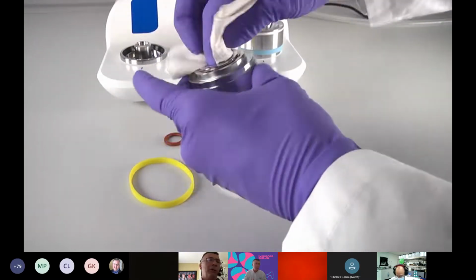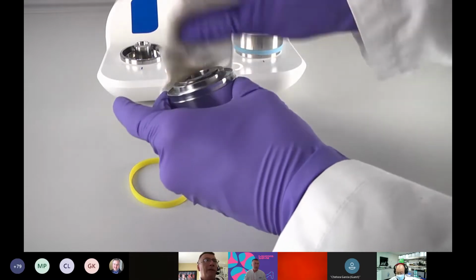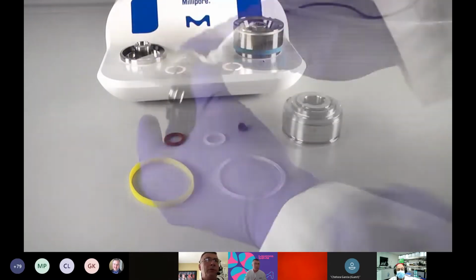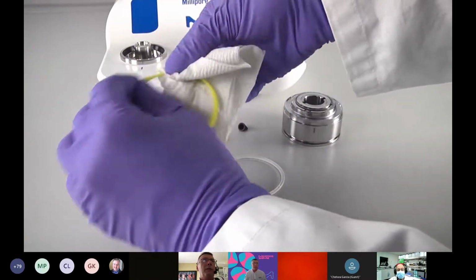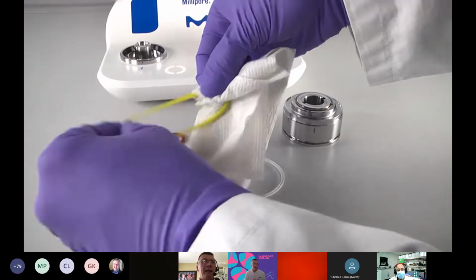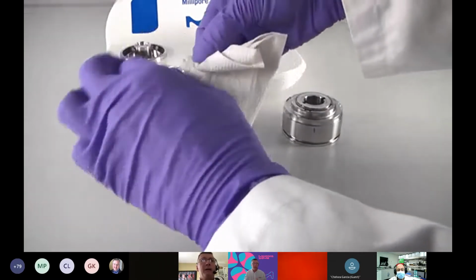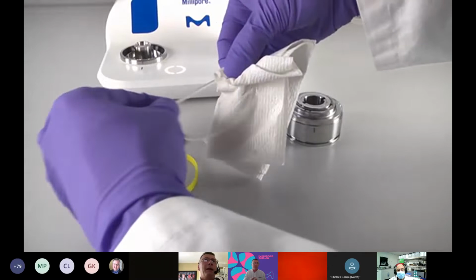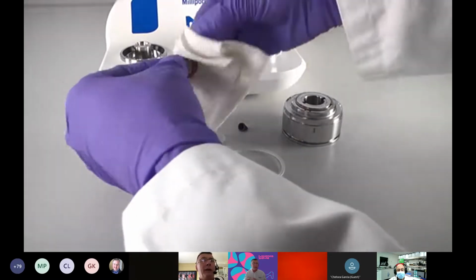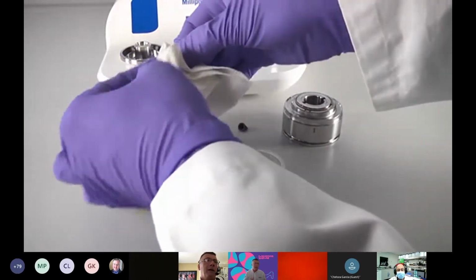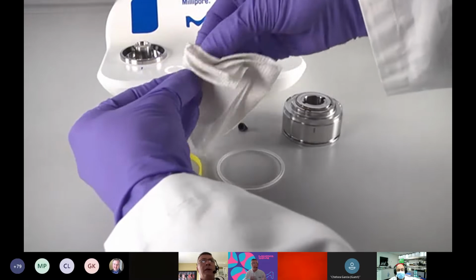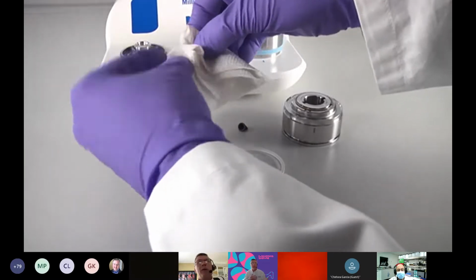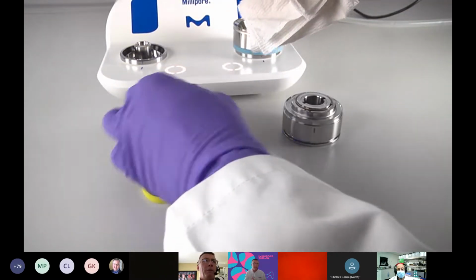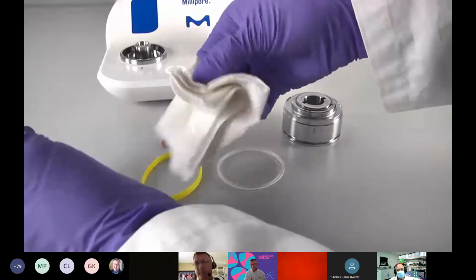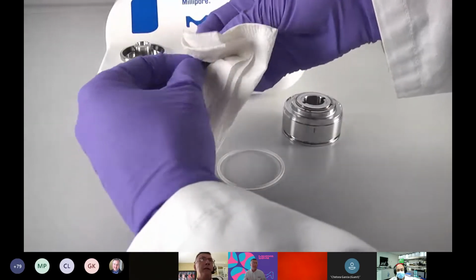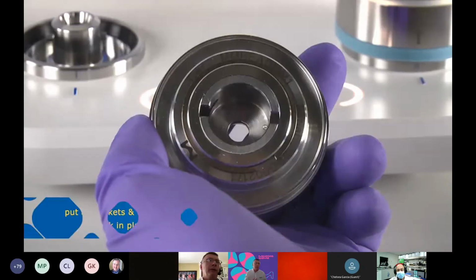There is no need for autoclaving, but we have found that there are some people who prefer to autoclave their units. What we're finding is that they're taking the gaskets and the O-rings and the check valve, and after they take it off the pump head, they're putting it into the same bag that they put into the autoclave and autoclave it complete. That way they have all of the pieces for the pump head that they need when it comes out of the autoclave, and then they can simply reassemble as they're going to do here.